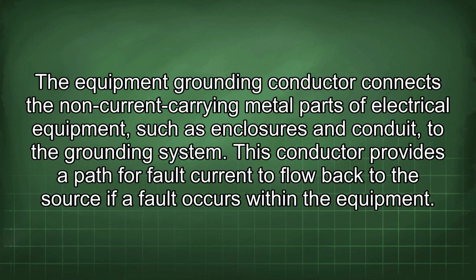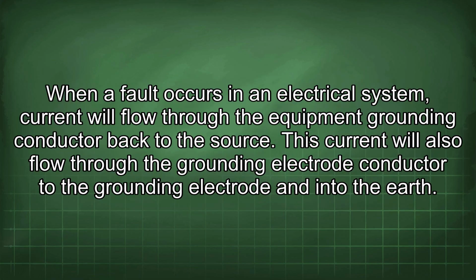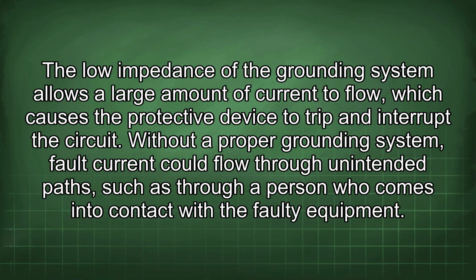The equipment grounding conductor connects the non-current carrying metal parts of electrical equipment, such as enclosures and conduit, to the grounding system. This conductor provides a path for fault current to flow back to the source if a fault occurs within the equipment. When a fault occurs in an electrical system, current will flow through the equipment grounding conductor back to the source. This current will also flow through the grounding electrode conductor to the grounding electrode and into the earth. The low impedance of the grounding system allows a large amount of current to flow, which causes the protective device to trip and interrupt the circuit.